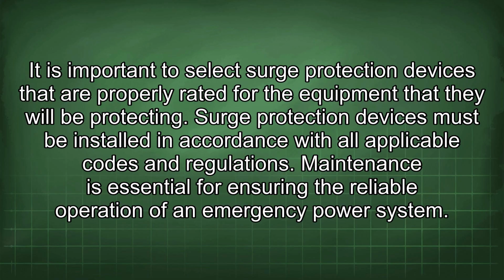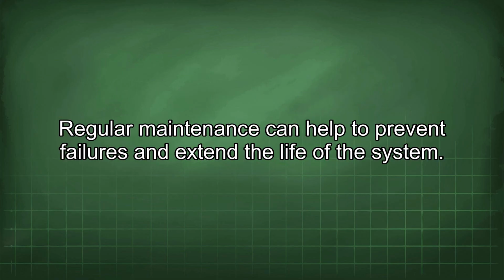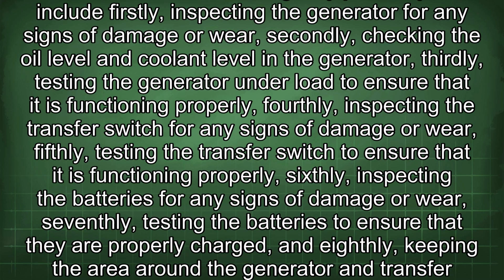Maintenance is essential for ensuring the reliable operation of an emergency power system. Regular maintenance can help to prevent failures and extend the life of the system. Maintenance tasks for emergency power systems include, firstly, inspecting the generator for any signs of damage or wear. Secondly, checking the oil level and coolant level in the generator. Thirdly, testing the generator under load to ensure that it is functioning properly. Fourthly, inspecting the transfer switch for any signs of damage or wear.